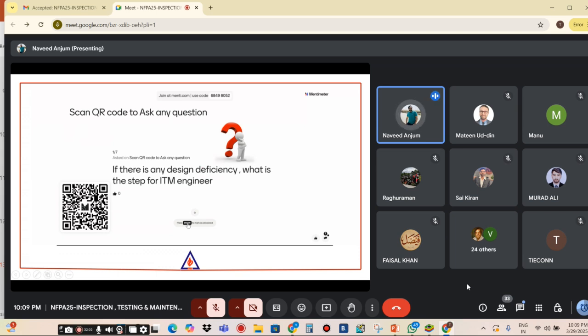If there is any design deficiency, what is the step for the ITM engineer? Basically, as an inspector, as I told you, in the NFPA-25 scope there is no scope to evaluate the design deficiency. If they have good knowledge, they can just communicate to the owner that in my opinion there is a design deficiency, but they do not mention it in their report. They will just check that the system can produce 250 gpm, 500 gpm, or that the hydrant flow is 750 gpm. You just accept it and test. If it is meeting the criteria, you will write down that it is okay.